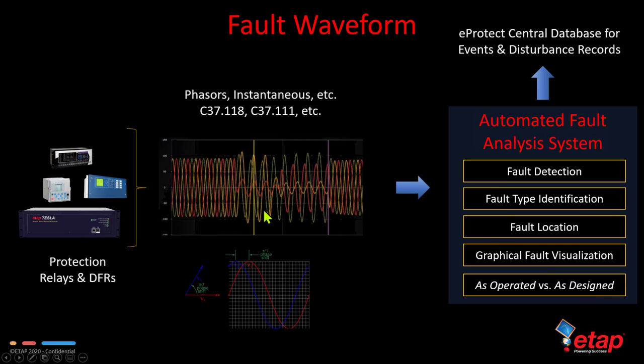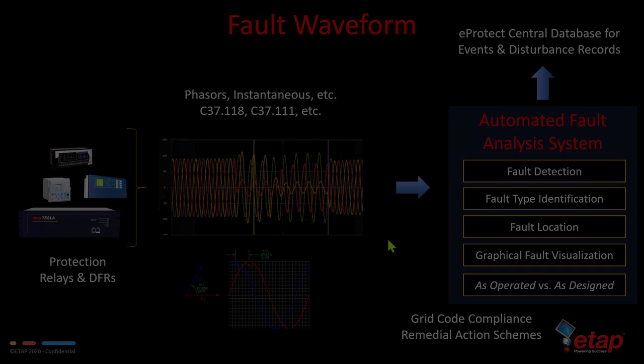In fact, the fault waveforms that are visualized in eProtect and saved can also be used for grid code compliance as well as remedial action schemes. And the RAS or remedial action schemes particularly use the phasor or PMU data for that purpose. So let's take a quick look at fault waveforms in action and how they are visualized and stored within eProtect.